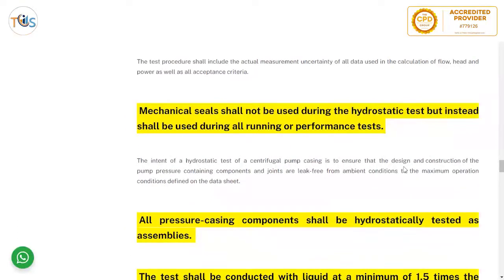Mechanical seals shall not be used during the hydrostatic test; instead, a slave seal is used to pressure-test the casing. This is because mechanical seals are not designed for hydrostatic test pressure, which is 1.3–1.5 times the maximum allowable working pressure and might damage the seal. Once the hydrostatic test is done, the slave seal is removed and the mechanical seal is installed for the performance test, where you want to verify the seal performs and does not leak under actual working conditions.